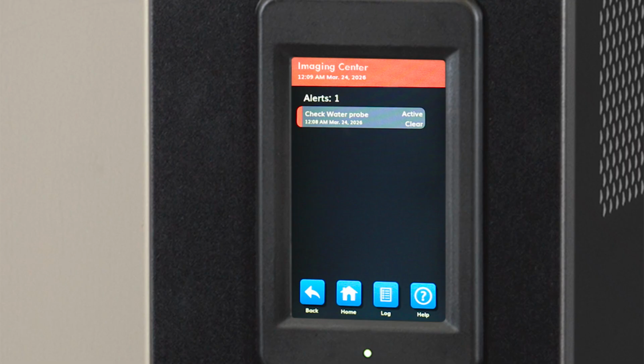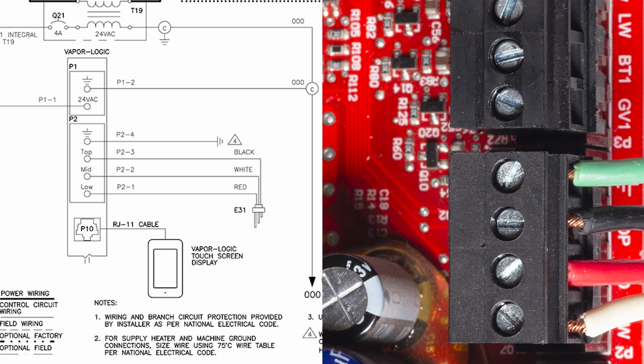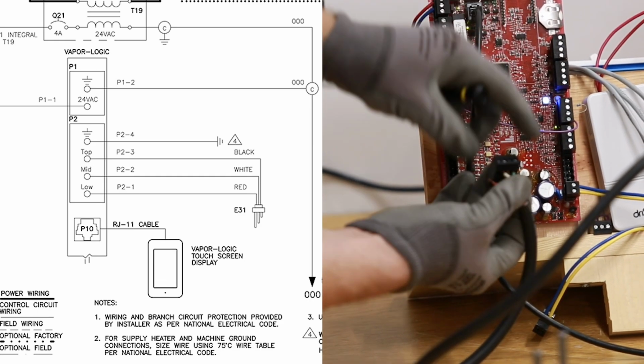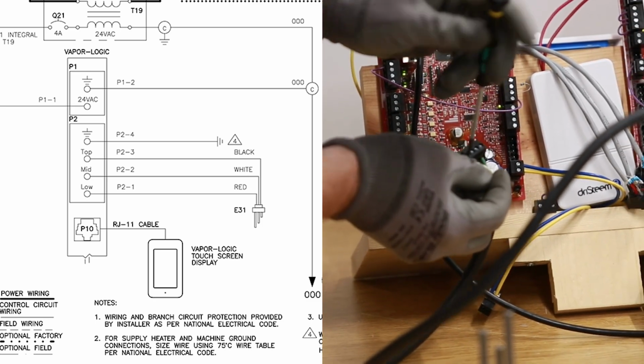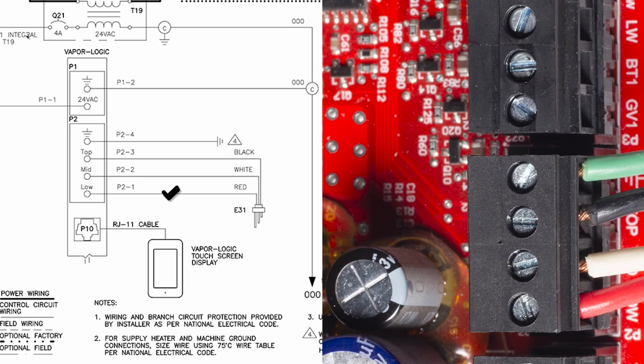If everything else checks out and you still get a check water probe alert, it's likely that the probe assembly is miswired on the controller board. Comparing the wiring diagram to the plug wires here, we determined that the red and white wires are reversed, which is what triggered this check water probe alert. To fix this, move the wires to their proper locations. The correct order on this plug is red, white, black, green.